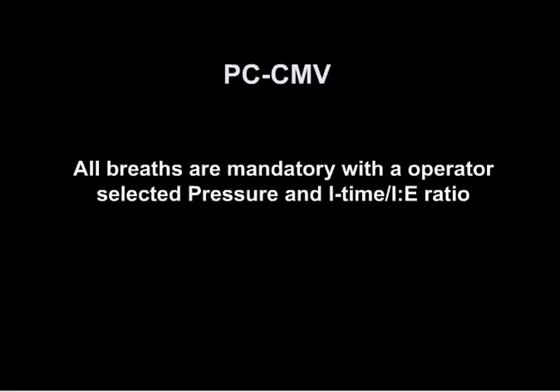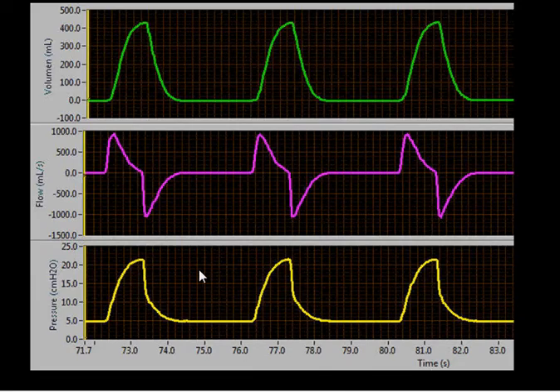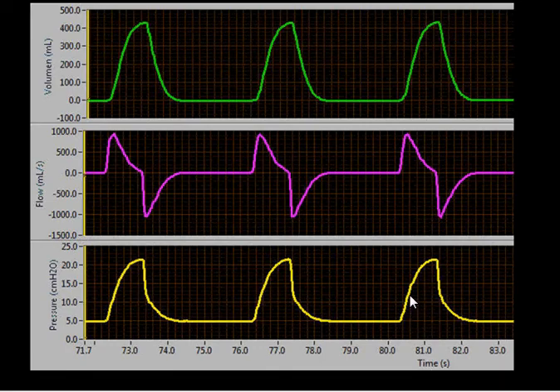Next, pressure control CMV. All breaths are mandatory with the operator-selected pressure and I-time or IE ratio. In the ventilator waveform graphic, there is a set inspiratory pressure for a fixed amount of time. If there are spontaneous attempts, the breaths will be delivered at a set pressure for a set inspiratory time or IE ratio.